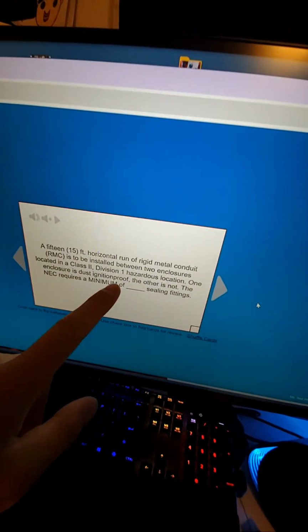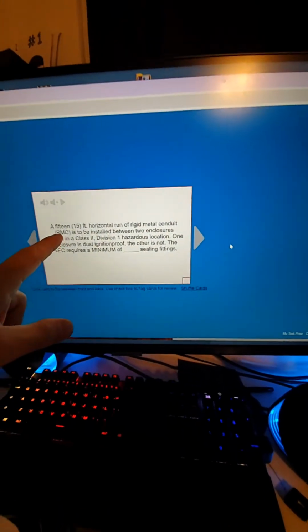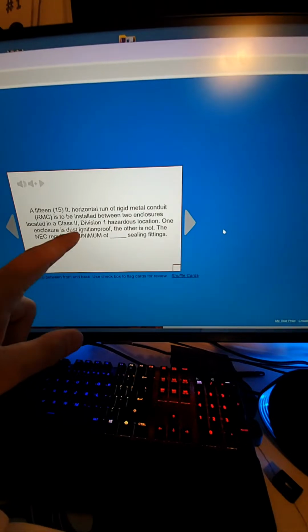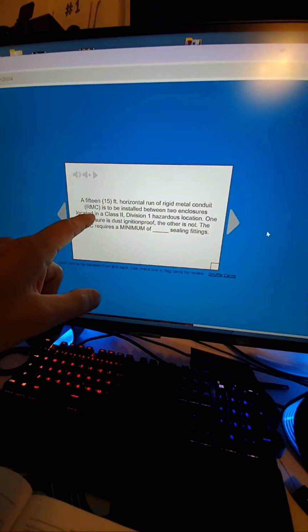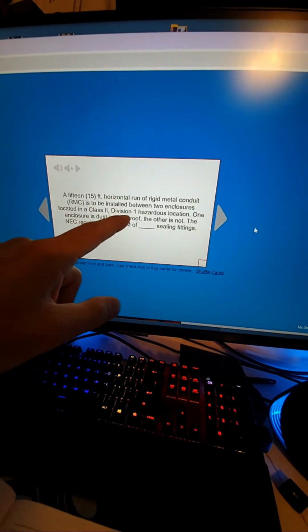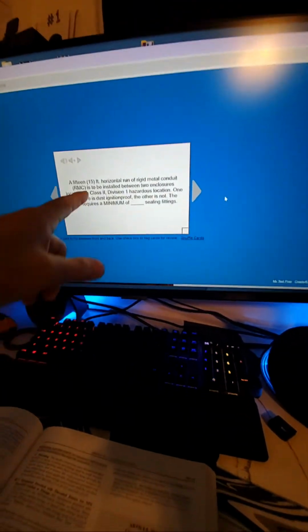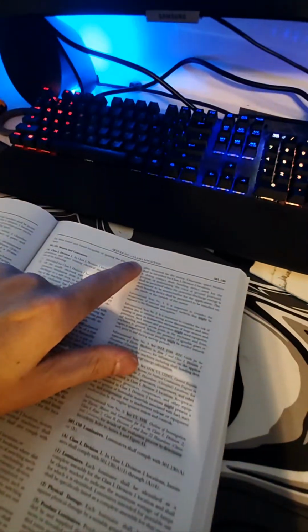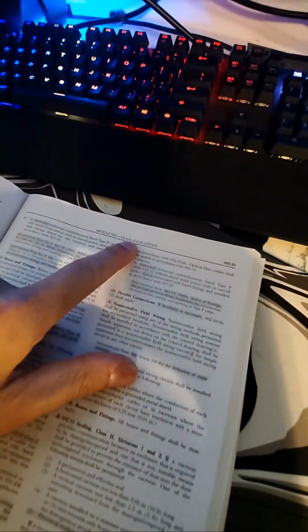So, Class 2 Division 1, we know it's going to be hazardous locations, which is typically Article 500. We could also look up the RMC, but a lot of times in your division of locations, RMC is a requirement. And since it's talking specifically about this Class 2 Division 1, and it says dust proof and so on, and sealing fittings, good chance we're going to find it in the 500s. So Class 2 Division 1, this is a Class 1. Still in Class 1. Class 2. Class 2 Division 2. Class 2 Division 1. I see the word RMC right there.